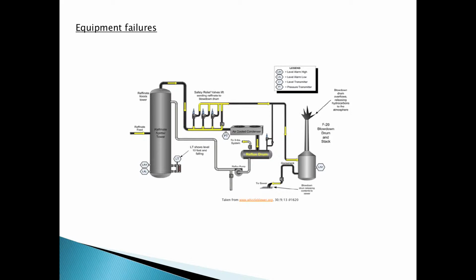The redundant high-level alarm, LAH 5102, which was the backup alarm if the other alarm did not function correctly, did not alarm when the set point of 78% was passed. These instrument failures blinded the DCS operator in making accurate decisions about the feed rate to the RAF tower.